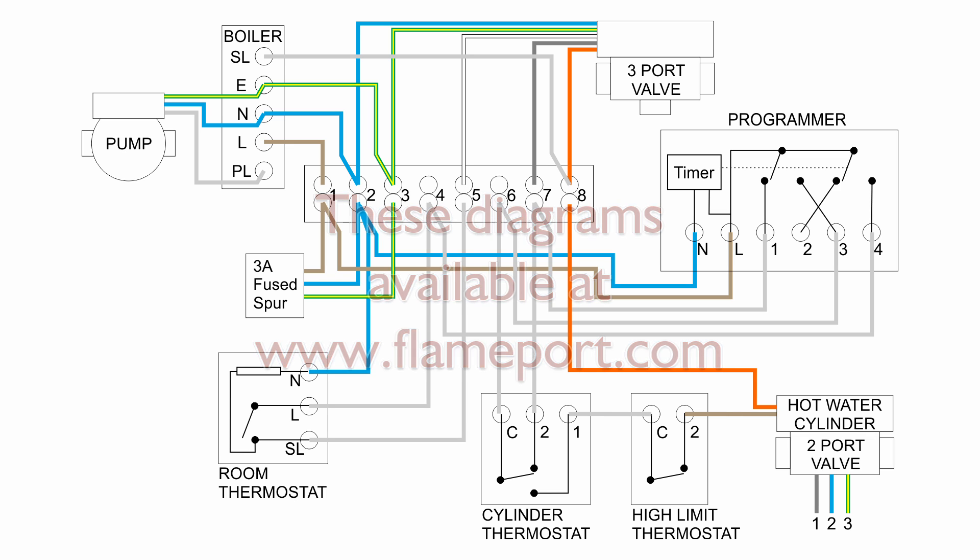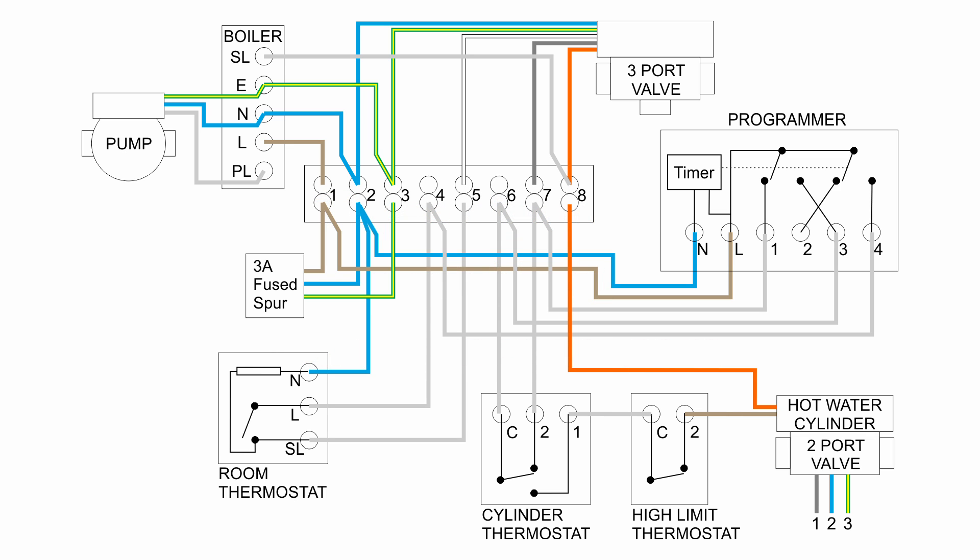So in terms of the actual wiring, the link there between the cylinder thermostat and the high limit thermostat is usually just a wire link between the two appropriate terminals, and then you're just using the output wires as we've got there. So the incoming there on the C and 2 on the cylinder thermostat, and then your output is 2 on the high limit thermostat. So although they're set out there, they are generally combined into a single device.